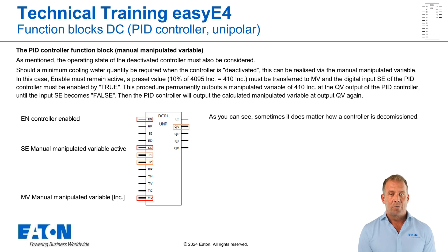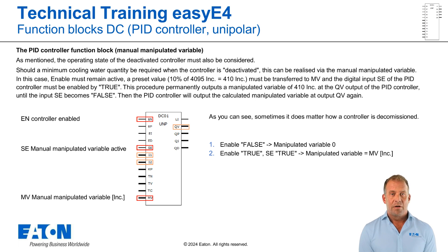Then the PID controller will output the calculated manipulated variable at output QV again. These are the two variants for putting a controller out of operation: first, enable false via manipulated variable 0; second, enable true, SE true via manipulated variable equal to MV in increments.